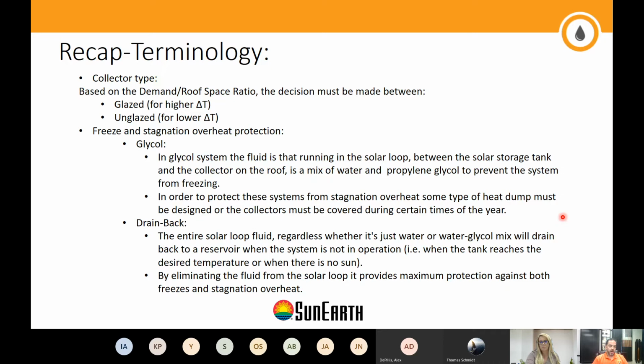First thing we need to do, you have to determine how much is your gallon per day consumption. What is your total daily hot water consumption? That goes through for every application, because whatever amount of energy that you're using translates to a delta T and a certain amount of water. Once we have that information, we can calculate the entire demand of the building.